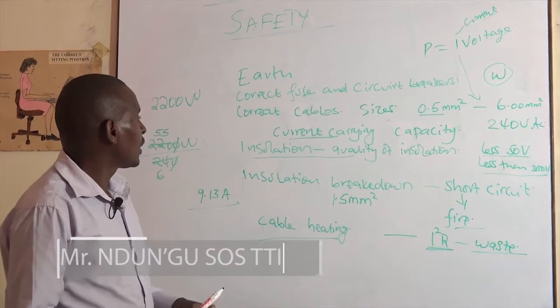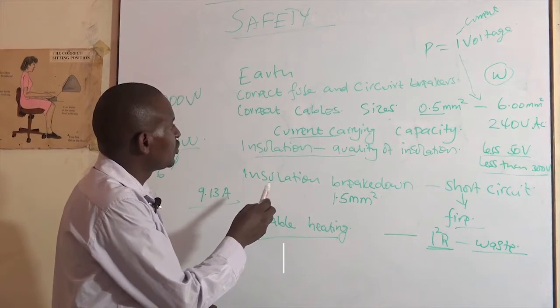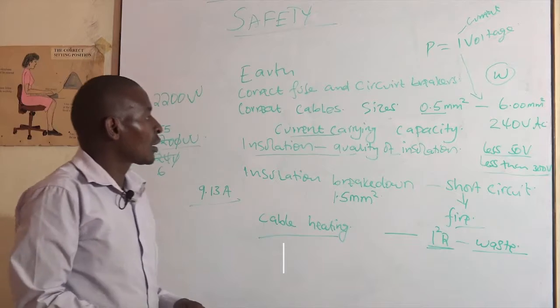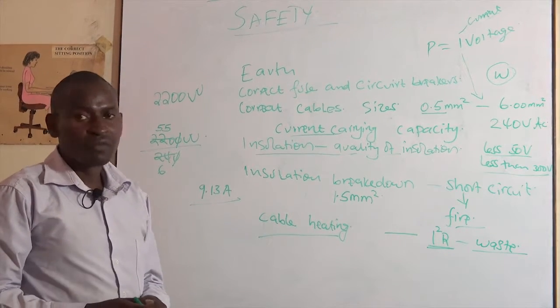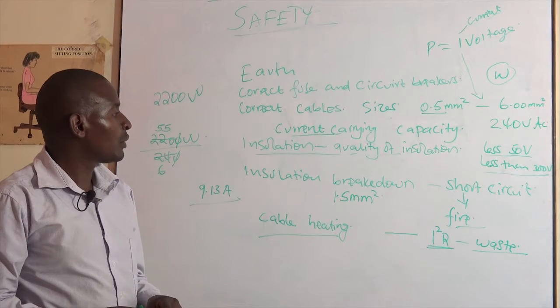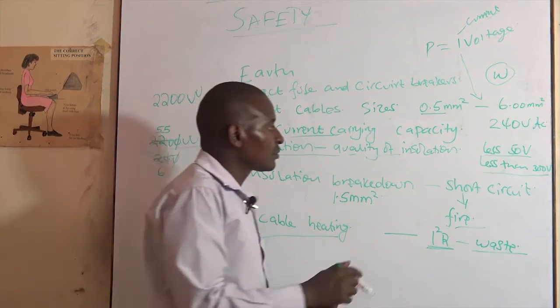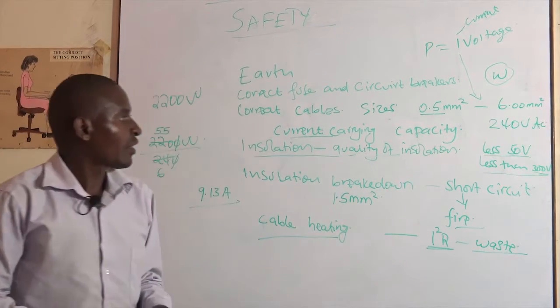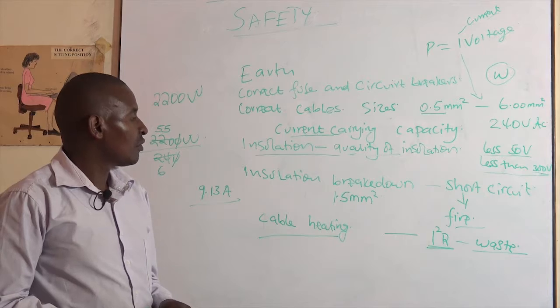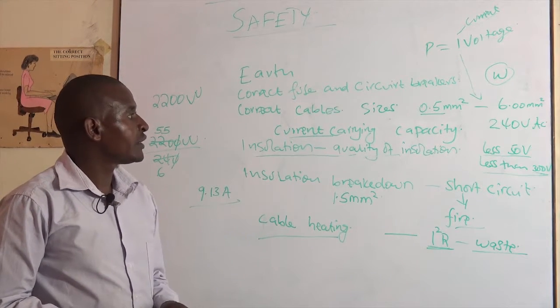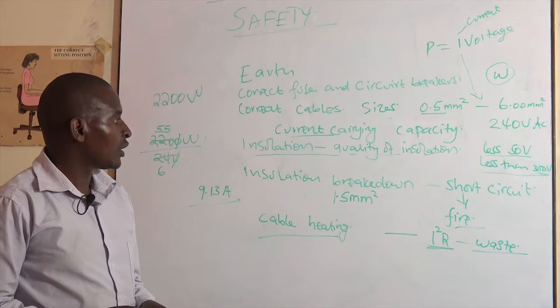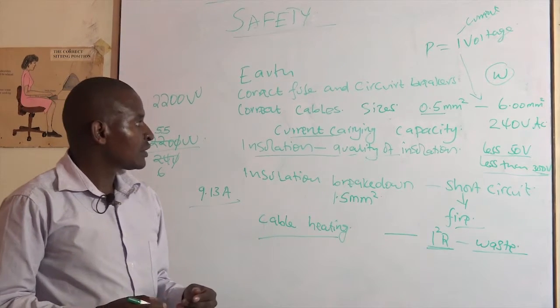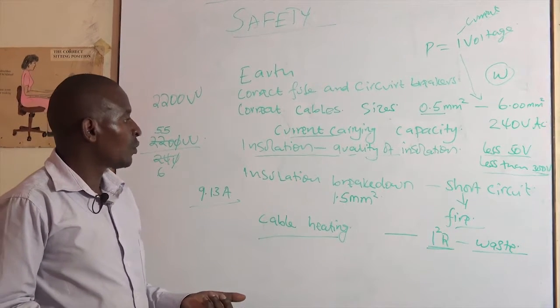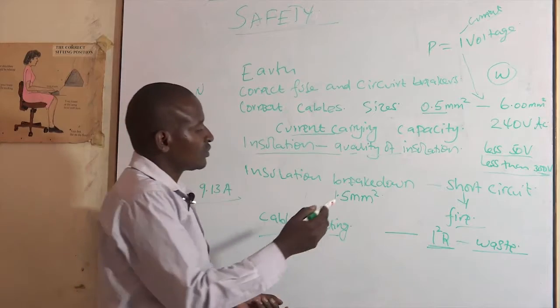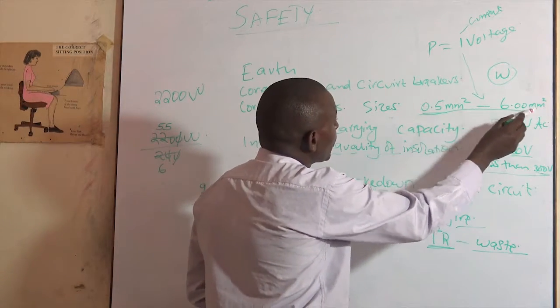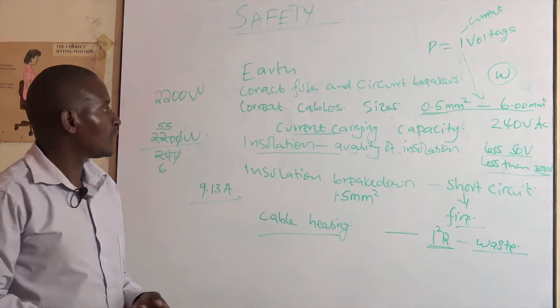The other issue is the quality of the insulation that might be chosen. But this one has not much problem, because most of the cables that we use for domestic installation are rated at 300 volts, which is quite safe compared to the 240 volts that we use for our domestic installations here in Kenya. But on the size of the conductor, that's something that should be noted very well.